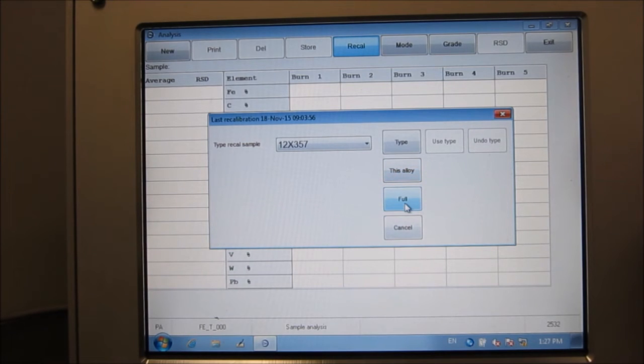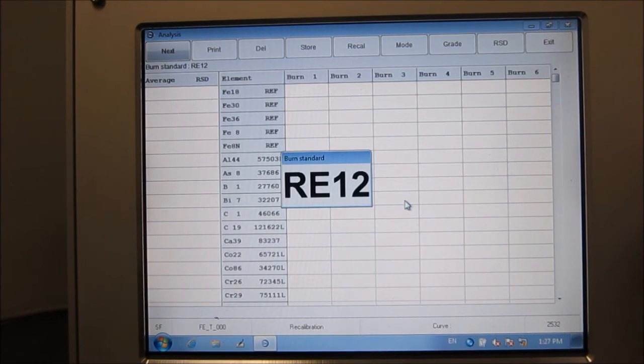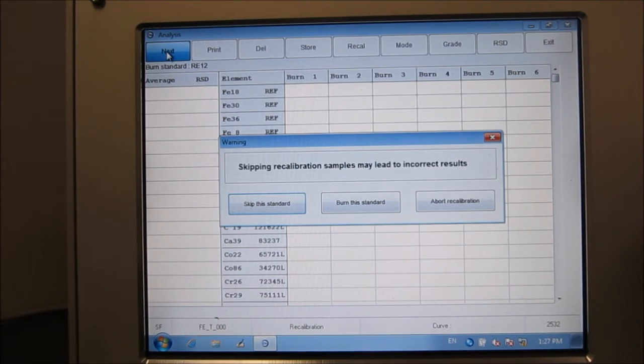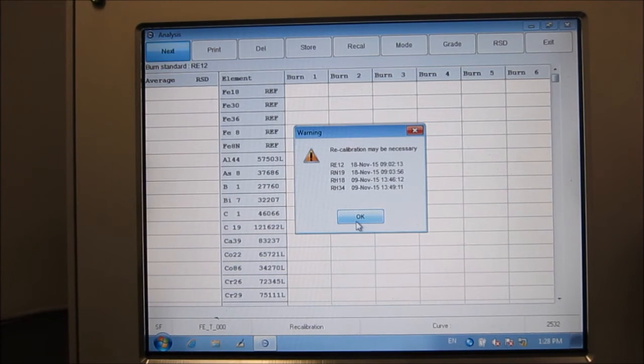So a full recalibration will be a recalibration for the entire matrix. Like for instance, if you click full now, it will do the entire recalibration for the iron matrix, and here it will tell you to burn standard RE12. Alright, so what we need to do now is actually to burn a sample as a standard, but if we do not have that, we'll click next and we say abort recalibration. Alright, but here it is again reminding me that there are calibrations that I need to do with these standards that I have.